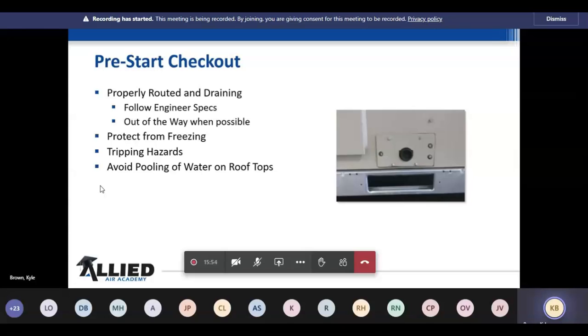So we want to follow the engineer specs. We want to keep them out of the way. And the one thing here that gets people is protecting from freezing. You would think, man, it's hot on a roof, why would I need to worry about protecting it from freezing? Because depending upon what application you're using, this air conditioning can run in freezing temperatures. If it's running in an industrial situation where you have machinery down below that may produce steam, like in a dry cleaners where they have the big iron presses and everything else going, you're going to have high humidity in there.